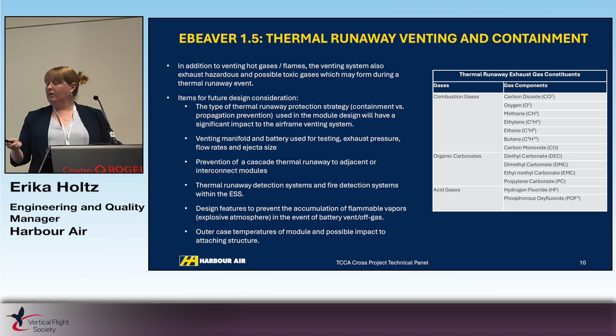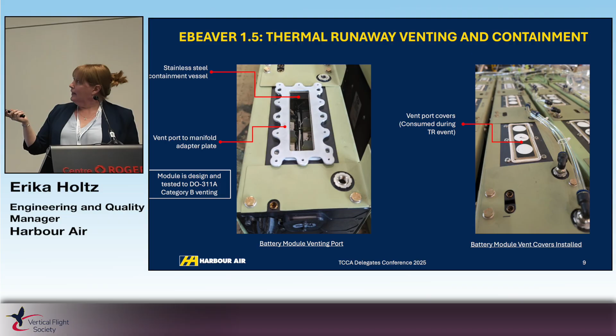In this one, though, if it goes into thermal runaway, it just allows it to cascade throughout the module - there's no propagation mitigation. That's a bit more about how the vent system actually works.